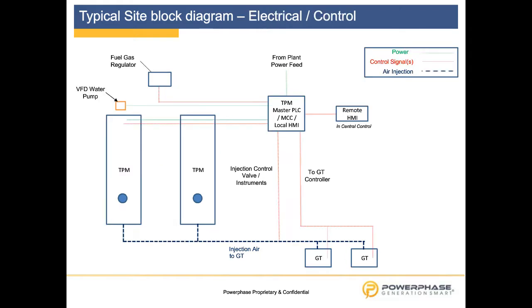The next picture will show us the site block diagram for the electrical and control. Here we have the interface of the electrical power. We would need from the plant 1 power feed, as our standard TPM has a parasitic load of close to 30 kilowatt, which is very low. So we would require a 3-phase 380 to 415 volt, 50-60 cycles power supply. We would bring our own logic. In the center you see the TPM master controller. We will bring our own motor control cabinet and the local HMI.